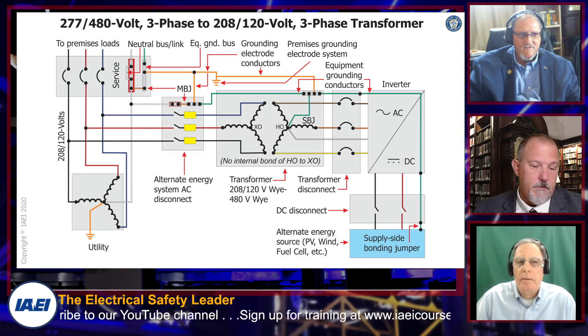I had an inspector call, doing site review, really concerned. He had a big box store with 2 megawatts of solar photovoltaic modules on the roof, 16 inverters at 480 volt output, going into AC combiner boxes, 4 AC combiner boxes, taking 460 amp breakers in, and then a 400 amp feeder out on the main lugs, going to a 1600 amp disconnect at the service. He basically said, do I have 16 separately derived systems? What do I have grounding and bonding wise, and how do I deal with all that?